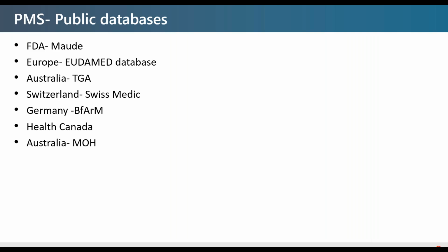So FDA has MAUDE, it should be capitalized, sorry, and then Europe, EUDAMED someday, we hope, Australia has TGA, Switzerland has Swissmedic, and then there's BfArM, Health Canada, and Australia has the Ministry of Health. So again, make sure that you're searching not only for your device, but any similar or equivalent products as well.